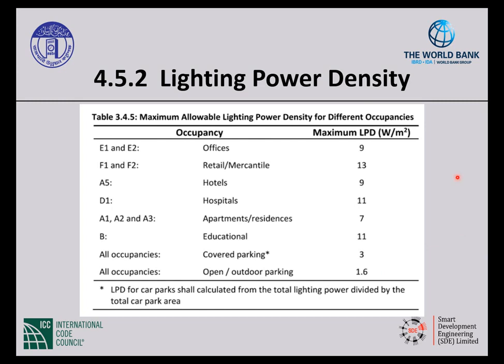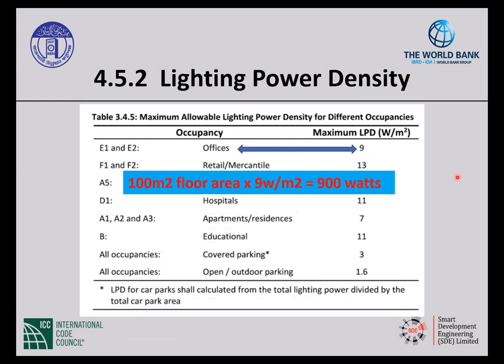So if we give an example, if we have an office building and it's allowed 9 watts per square foot, and say I have 100 meters floor area, right? So 100-meter floor area would say that I could have 9 watts per meter. I could have 900 watts in that area. I could do it by each individual area, or I could do it by the whole building. So maybe I have 1,000-meter floor area, then I have 9,000 watts for the whole building. I might have mixed occupancies, so I could say, how much of the square footage is office, how much of it is educational, how much of it is parking. So you could calculate each separately that way. But that's how you use that.